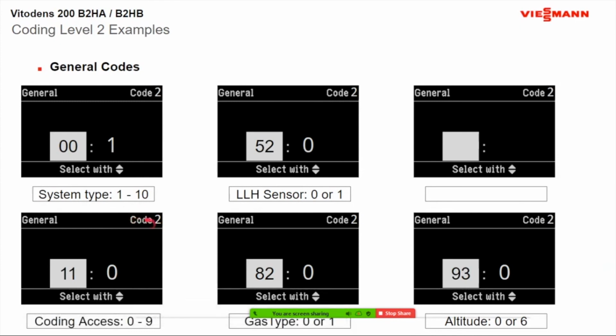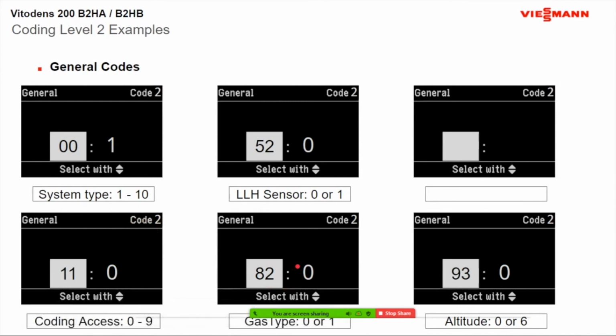But what you're going to see is that code 2 at the very top here is going to come out of the picture, and you're going to see a skeleton key come up here. So now you know that you've unlocked the door. Now you can go to address 82 to make that change from 0 to 1. Once you put the 1 here and you turn the little dial on the gas valve itself from 0 to 1, you now have converted your boiler over to propane.